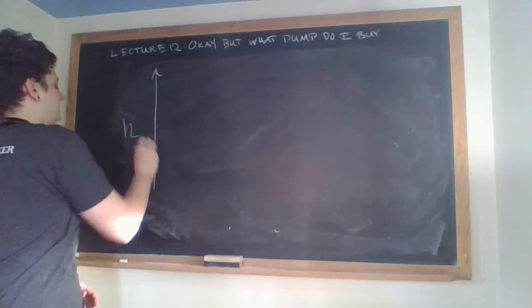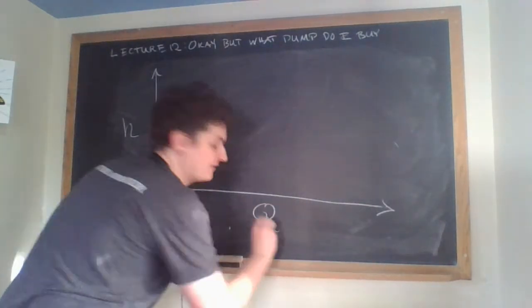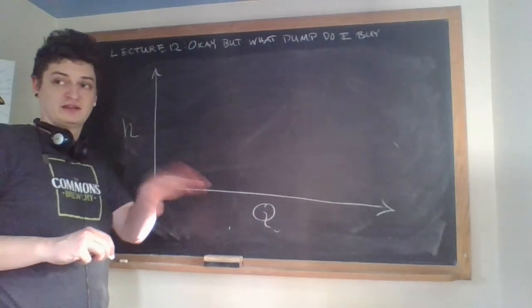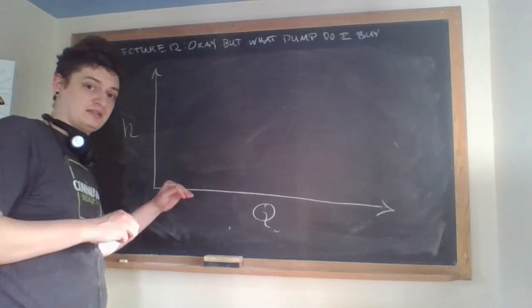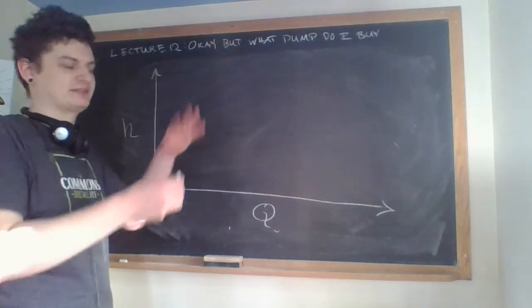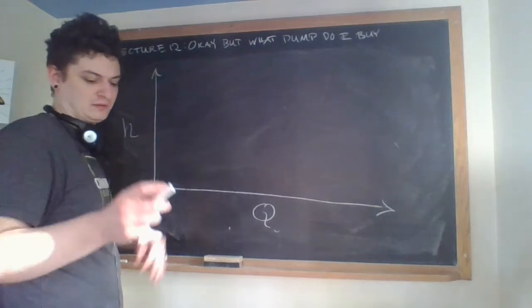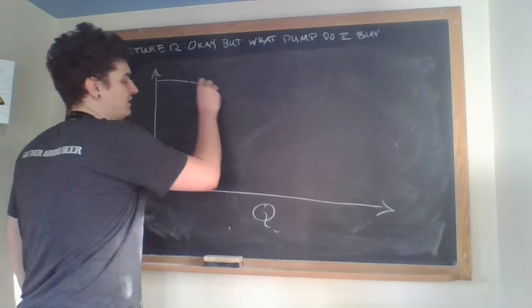Okay, so here's where I wish I had a whiteboard for all the graphs. All of these things may be together. I'm not going to draw the net positive suction head required. Why? Because it's usually so low down here that you're usually going to satisfy it. Really tight systems or large systems could behave that way, right? But for your project, you really just need to think about these curves.